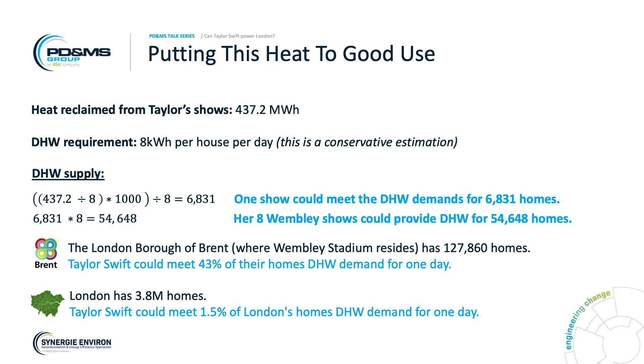But can it really though? The question is, why has it not been used for space heating? The reason is because you have 2 types of heat: low grade and high grade. An ambient loop is low grade heat - the name is ambient because it's ambient air temperature, between 10 to 30 degrees. It's great for washing your hands, great for having a shower. However, if you want it for space heating, you have to top it up to make it high grade heat, using a ground source heat exchanger like we saw earlier, heat pumps, top-up boilers, etc. That's why it's easier not to use ambient loop for space heating - it just needs an extra step, but you can still use it.